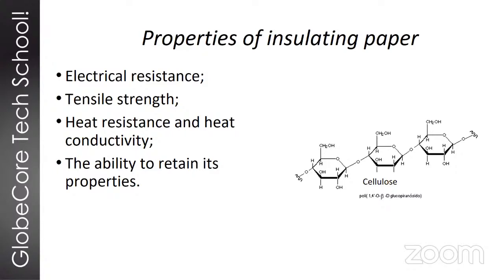So insulation paper must be resistant to thermal effects, resistance to heating, but it should also have the ability to conduct heat. And we know that paper is quite sensitive to temperature, so increased temperature in a transformer is actually enemy number 2, only followed by water in the transformer. Increased temperature in the transformer causes accelerated aging, and the performance, the characteristics, the condition of the paper in the transformer cannot be restored. Once it's damaged, it's done. It cannot be restored. So once the paper loses its performance, it loses its quality, and obviously we now face a significant reduction of life expectancy for the transformer.